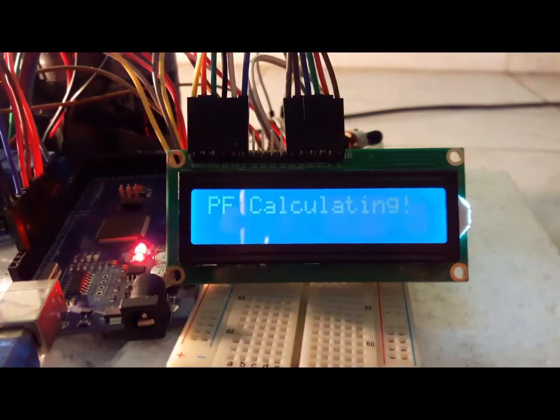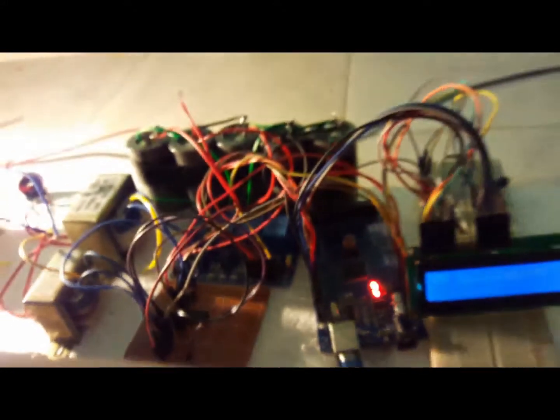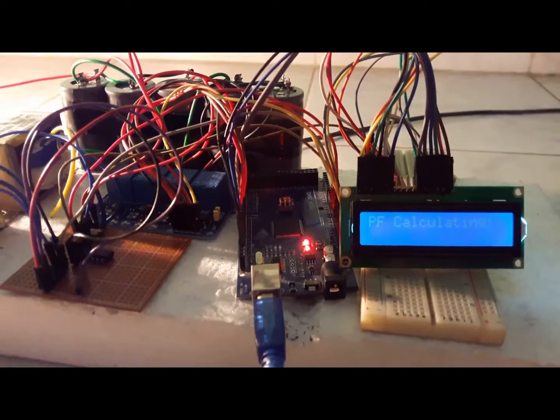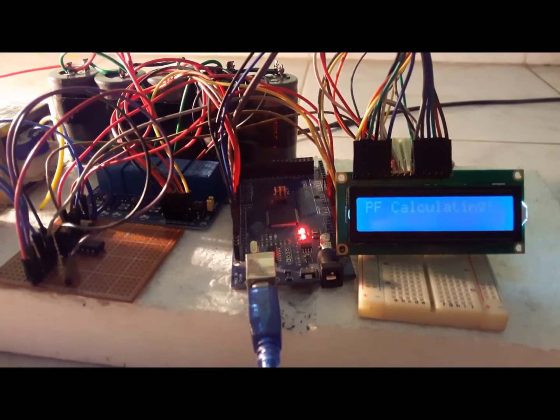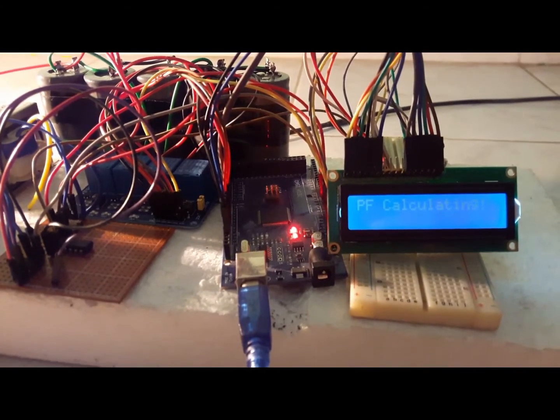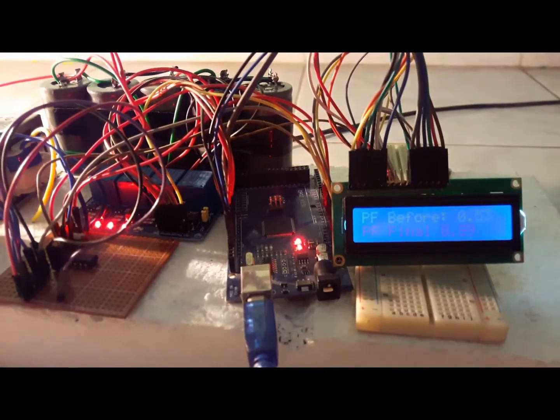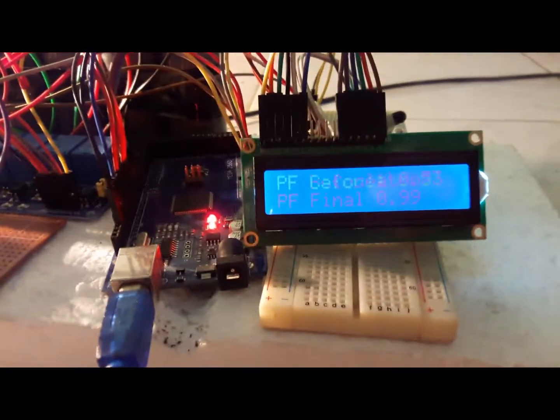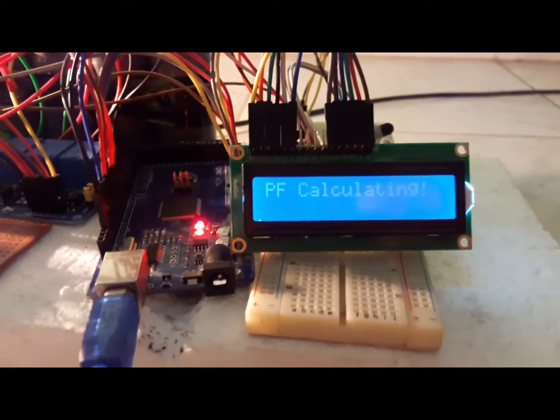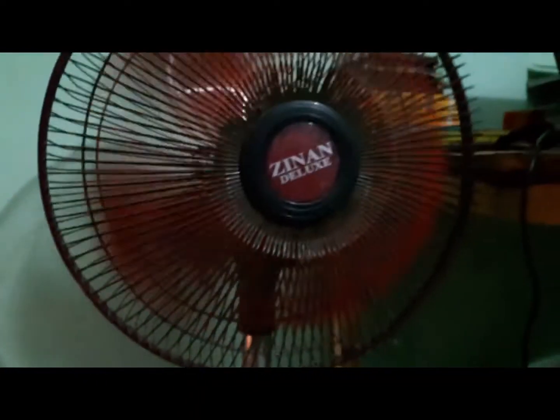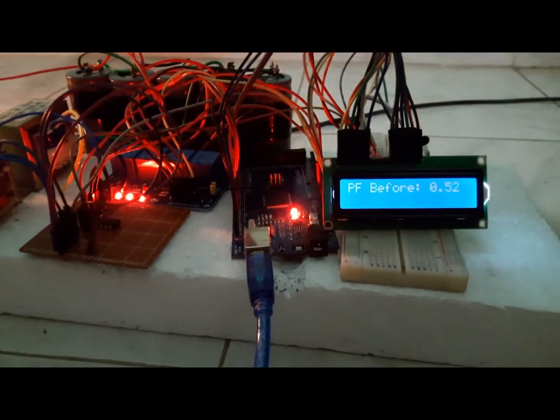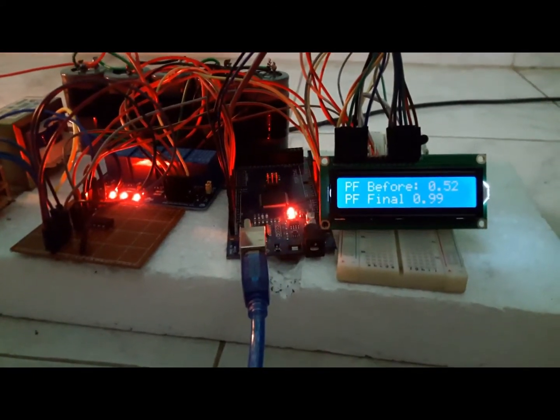Now we will observe the same process for a second time, and now we especially see how relays work to improve power factor by switching. It is calculating. Now we can see only 2 relays are active, actually 3. Now we can see all the 4 relays are active.